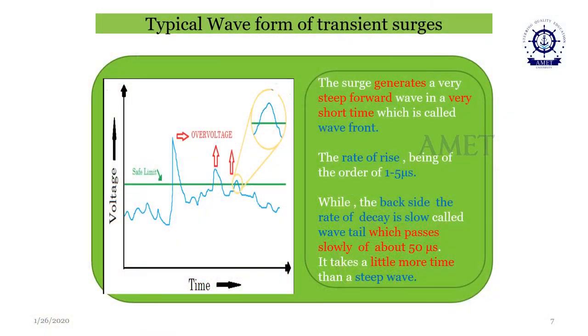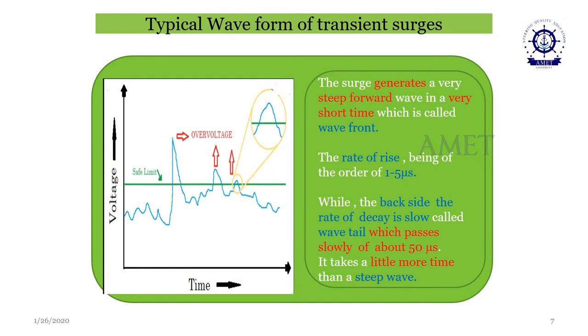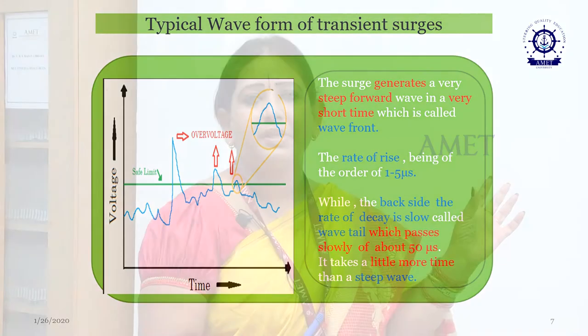This overvoltage has two parts: the wave front and the wave tail. You can see the waveform is very sharp and rises very rapidly, at a rate of about 1 to 5 microseconds. It's in the microsecond range. Similarly, on the other side, there is a decay of the overvoltage, which is very slow compared to the wave front. This is called the wave tail, and the decay time duration is about 50 microseconds. This is a typical structure of switching surges, impulses or transients.